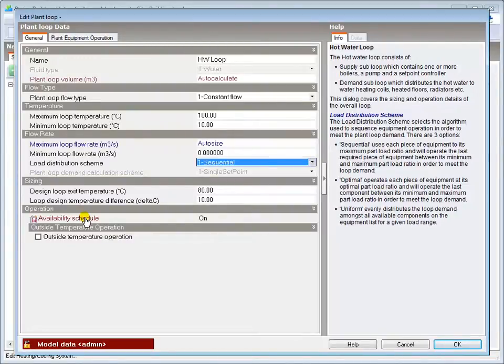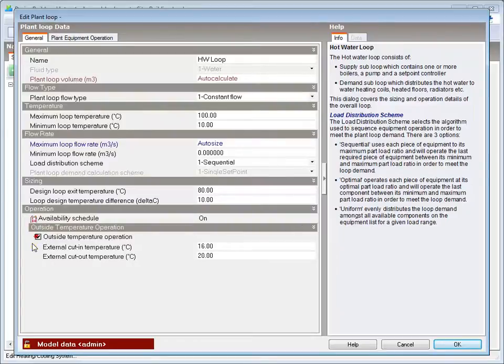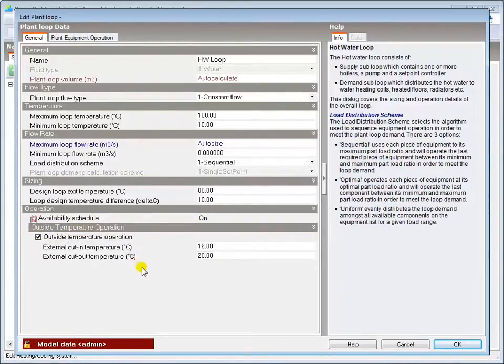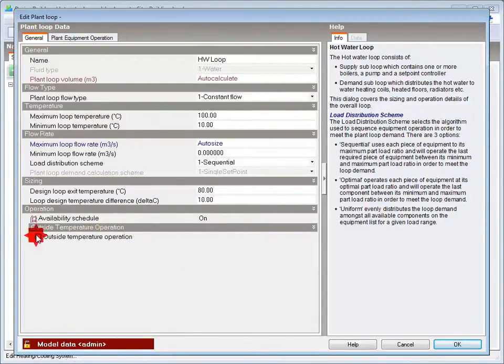The availability schedule is set to on and determines whether the hot water loop is available during the simulation. This can be modified using the external cut-in and cut-out temperatures to prevent plant wasting energy by frequently cycling on and off at very low loads.